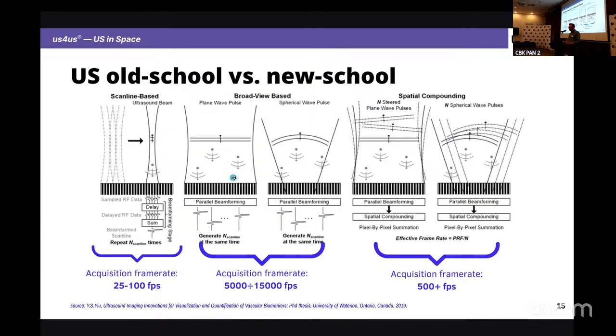Novel methods that we and most researchers are using right now, and which are slowly but surely migrating into medical devices, use plane wave imaging or compounded plane wave imaging. In general, those methods are known as ultra-fast ultrasound. Ultra-fast in the sense that, of course, the speed of ultrasound is the same independent of the method, but the acquisition is much faster, because we are not casting so many focused beams. We use an unfocused beam, and from a single transmission and reception event we can reconstruct the whole picture, with lower quality but much faster. So this is what you are seeing: the frame rate can go between 5 to 10K.